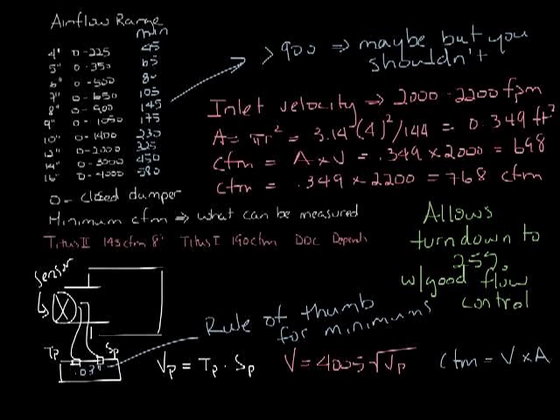So that explains how to size your primary air inlet. So if you're sizing a single duct box or a dual duct box, because the inlet size equals the unit size, you're pretty much done. In a fan box, the inlet size is only half the unit size. So now let's talk about how to size the fan in a fan box.